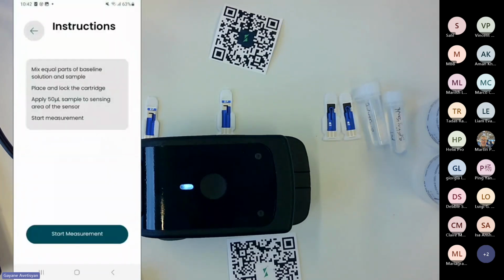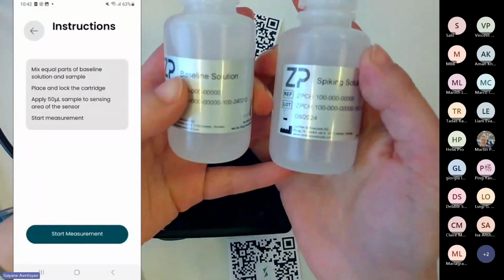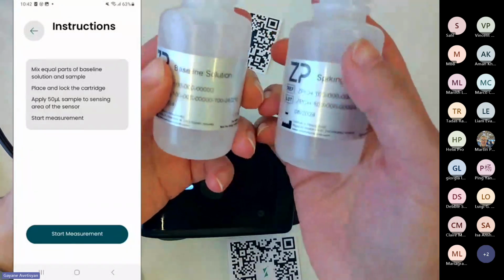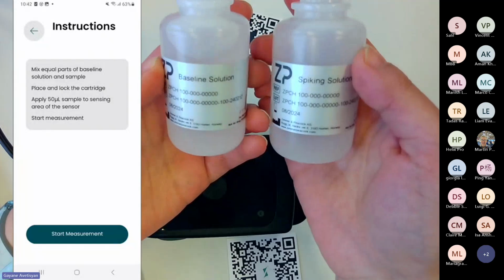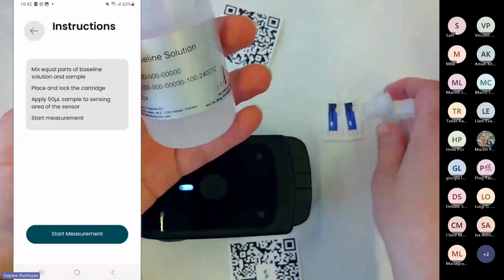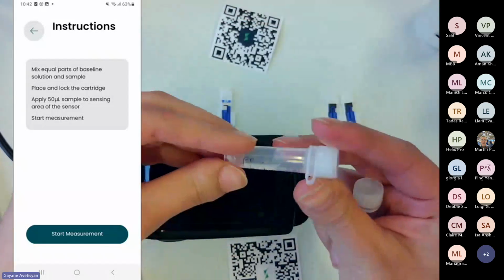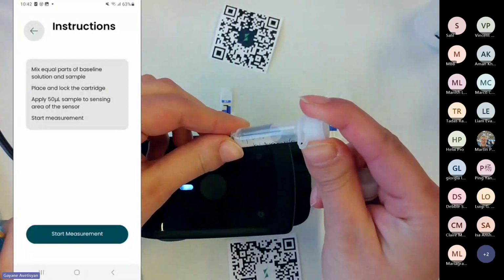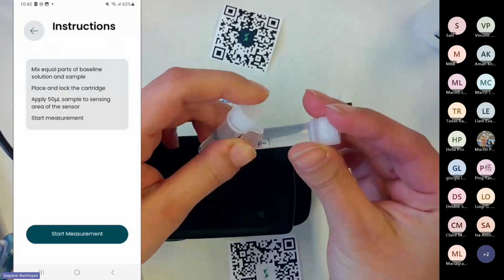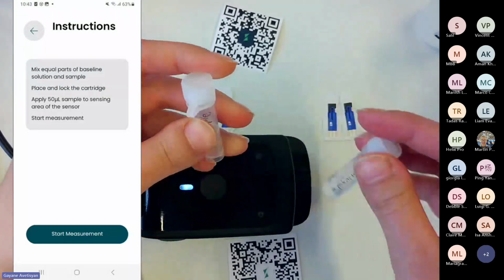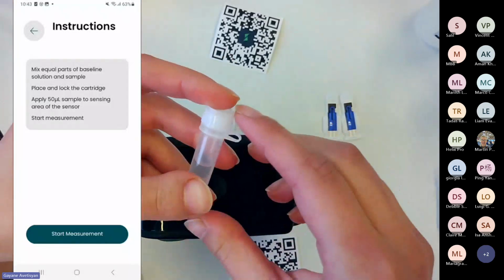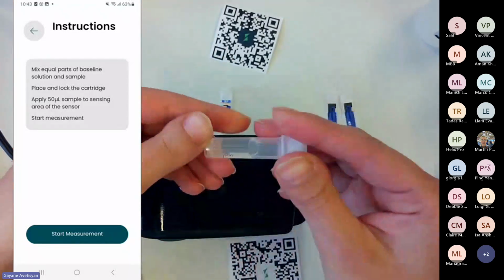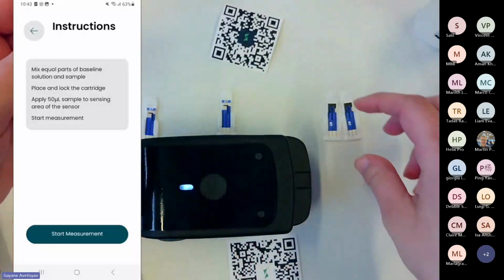So when I go to assay, the first thing that I will need to do is to mix solutions and prepare them. So when we are ordering the potassium SenseItAll kit, it comes with 2 solutions, baseline solution and spiking solution. What we need to do is to mix these solutions with the sample solution with a 1-to-1 ratio. So right now I have 2 solutions prepared. This one is baseline solution mixed with my testing solution, and this one is spiking solution mixed with the sample solution. As the instruction says, mix equal parts of baseline solution and sample. I already did that, and now we will need to place and lock the cartridge.